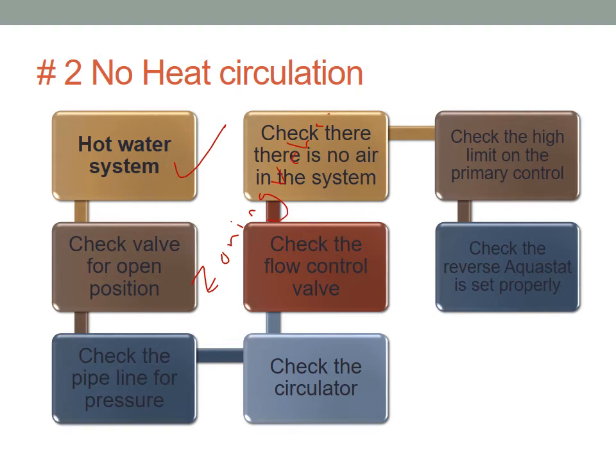Check the pipe line for pressure, make sure there's enough pressure. Water is very heavy, guys. If we don't have enough pressure to push the water on, probably the pump will turn on, but no water will circulate because probably the pump is weak. So sometimes things are working, but they're not working the way they're supposed to be.